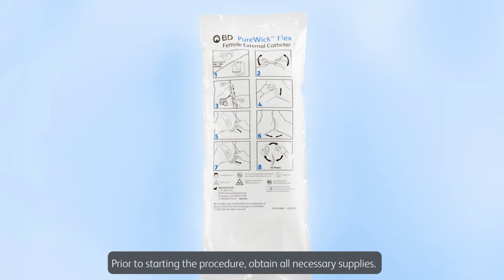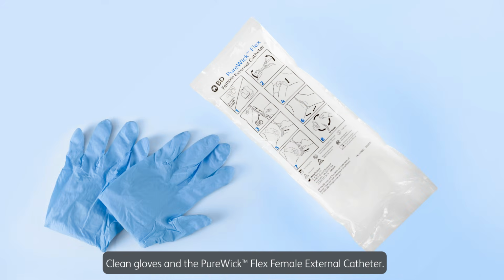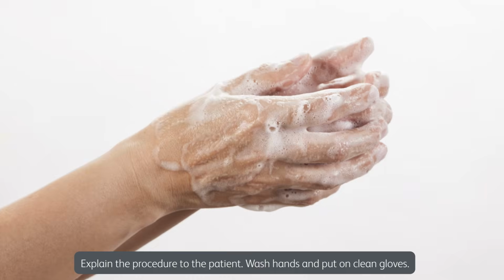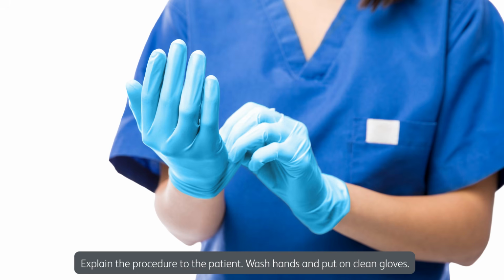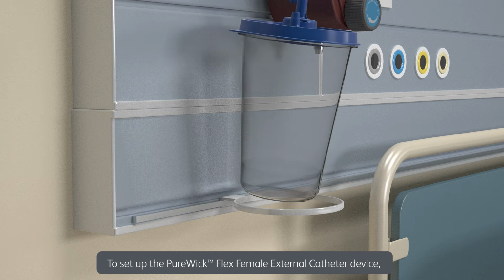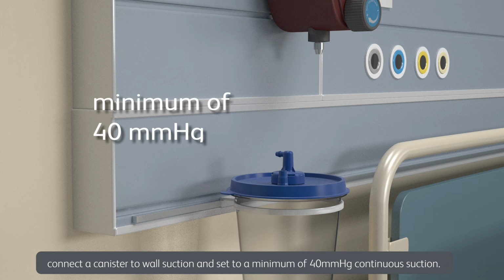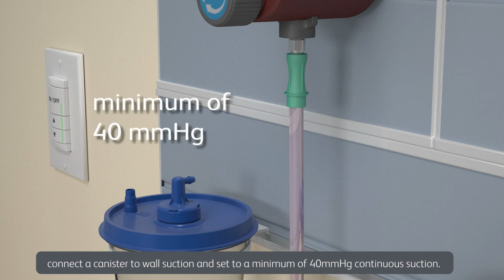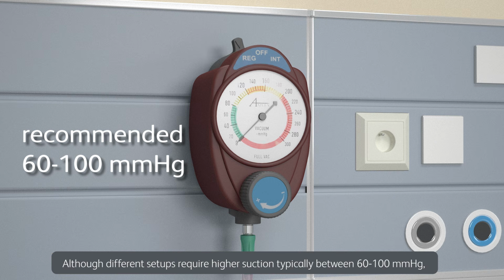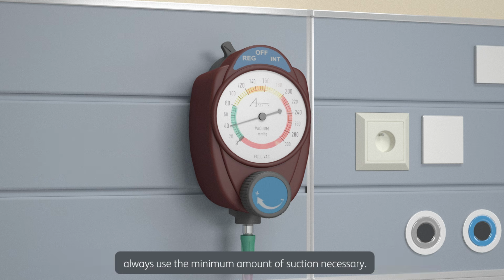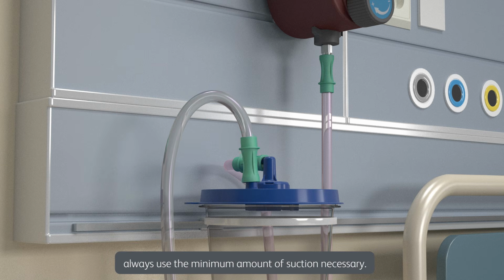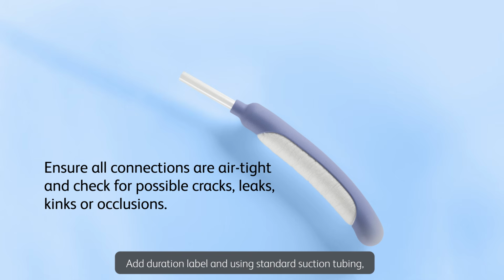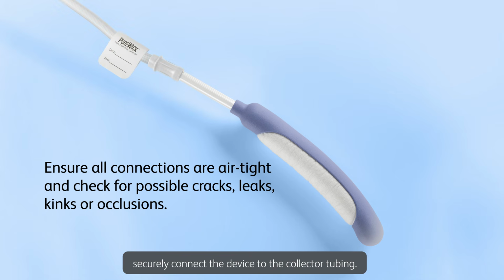Setup. Prior to starting the procedure, obtain all necessary supplies: clean gloves and the PureWick Flex female external catheter. Explain the procedure to the patient. Wash hands and put on clean gloves. To set up the device, connect a canister to wall suction and set to a minimum of 40 millimeters of mercury continuous suction. Although different setups require higher suction, typically between 60 and 100 millimeters of mercury, always use the minimum amount of suction necessary. Add the duration label, and using standard suction tubing, securely connect the device to the collector tubing.